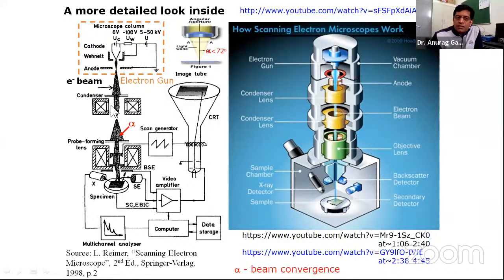And then these are condenser lenses, and these are the scan generators or scanning coils. They can make a small movement in the electron beam. And these are the detectors, the secondary electron detector and the backscattered electron detector. The output of this detector is sent to a video amplifier, which will amplify the signal. Then it will pass through the CRT, and over the CRT the image will be produced.